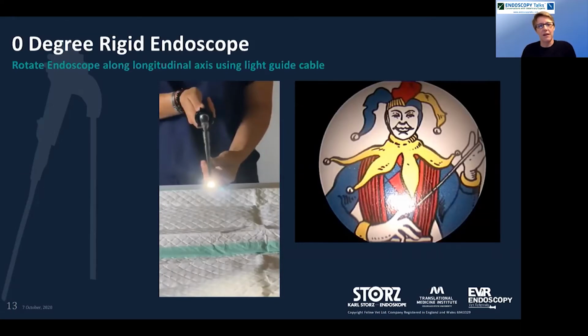And as you can see, when I rotate the light guide cable around, the Joker's head, this is just for illustration, it pretty much is still in the center of the image. So as you can appreciate, it's quite intuitive. But when you're working in a tighter space, that's going to be very limiting because you're not going to be able to see peripherally what's going on. And in order to see any pathology in the periphery, you'll have to actually move your endoscope left, right, up, and down. And what happens by doing so is you cause significant soft tissue damage. That's particularly true when you're in the nose or even in the urogenital system. You potentially could tear the tissues. So it's quite dangerous.